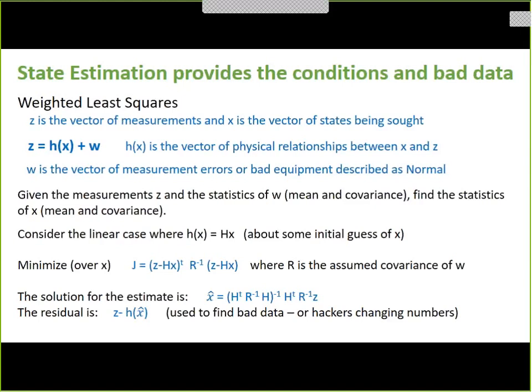downstream, like who he was doing. Now you could mess with the GPS system and change the... Right. Well, but a lot of the state estimation isn't using the PMU values for validation, the measure. That's a big discussion. The question is, should you use PMU data to make the state estimation better, which it would, or should you use it as a check on the state estimator to see if there's an error somewhere or a hacker? Because the PMUs give you state measurements. We're doing state estimation. So in principle, if you have enough PMUs, you don't need a state estimator because you're measuring everything. Now, again, it's state measurements. It's like, do you believe it or you don't?